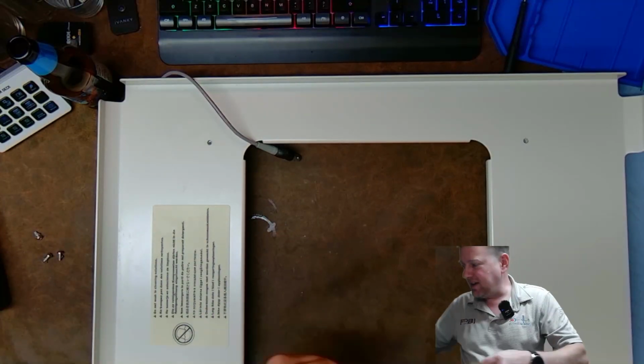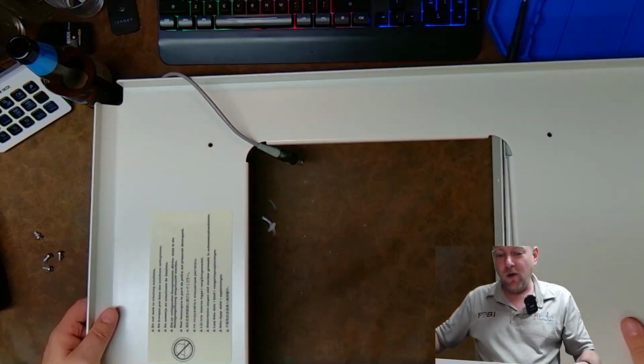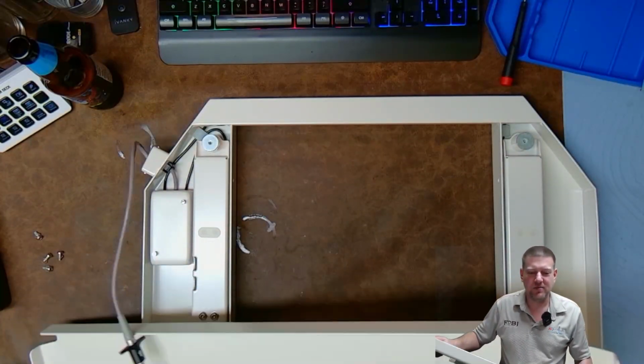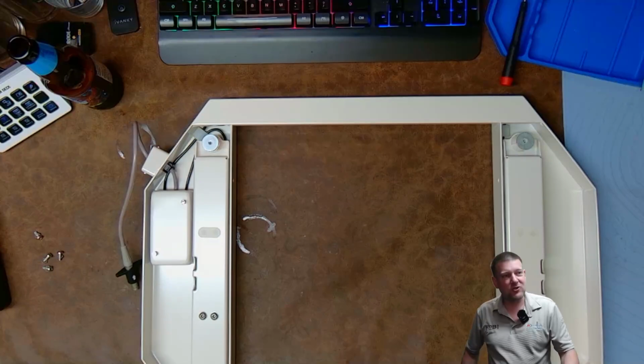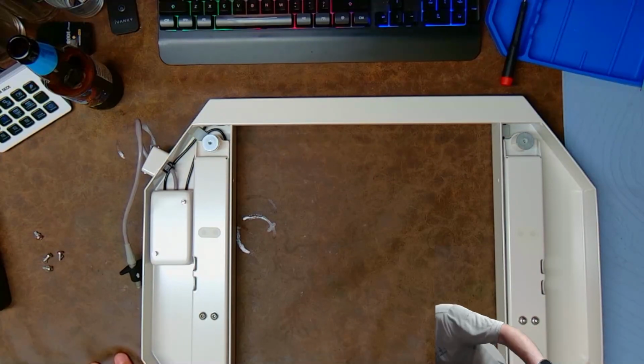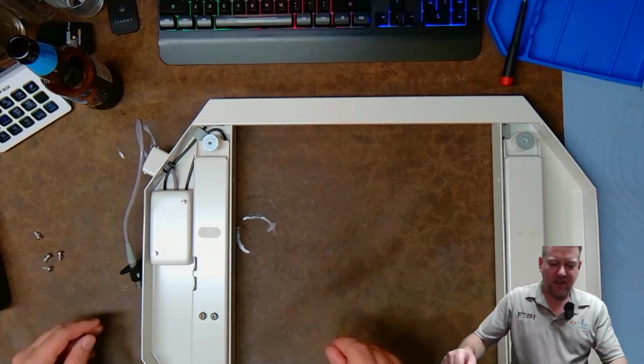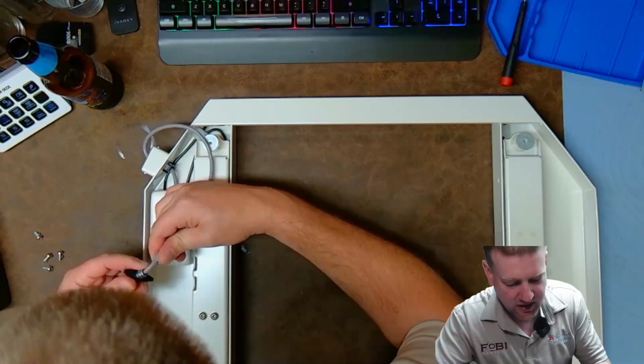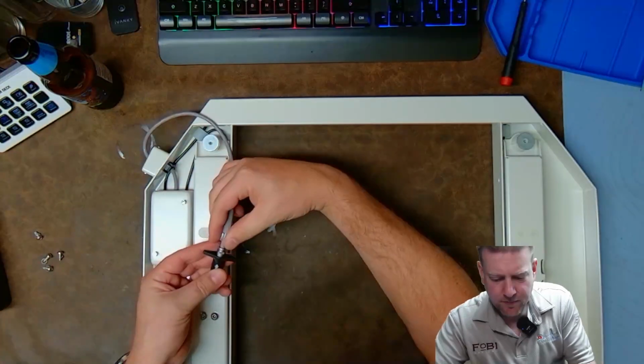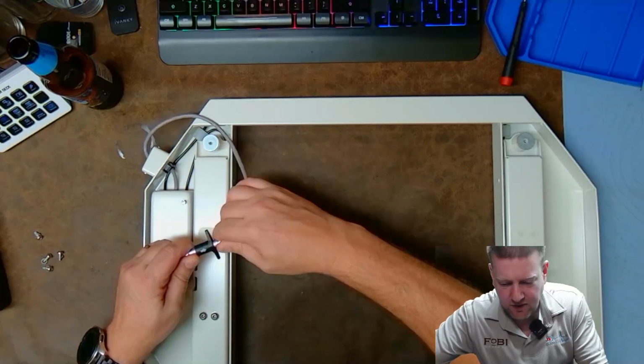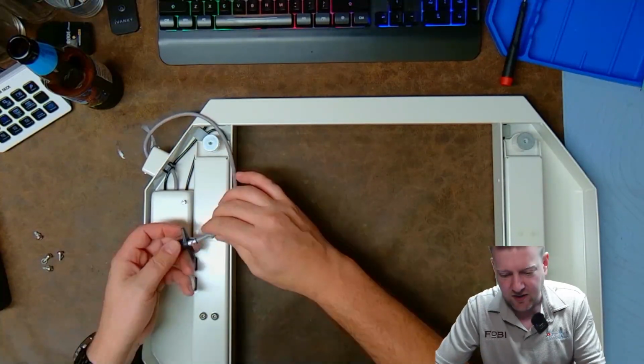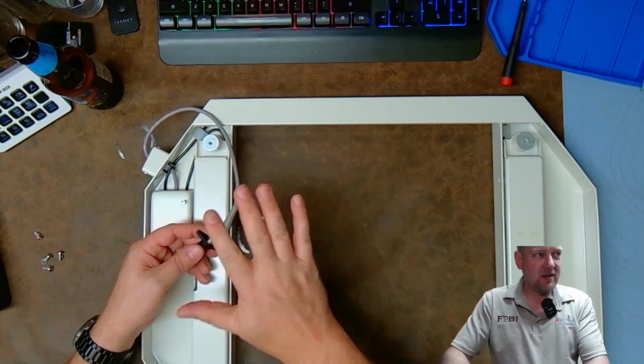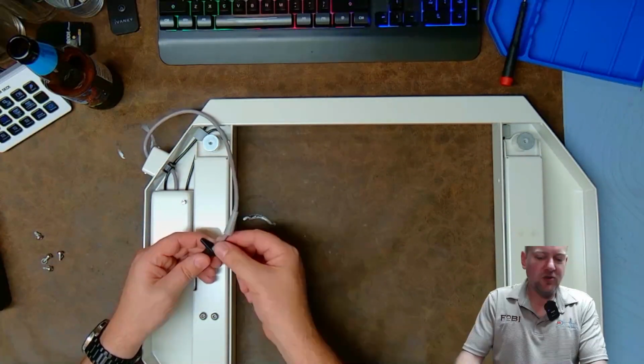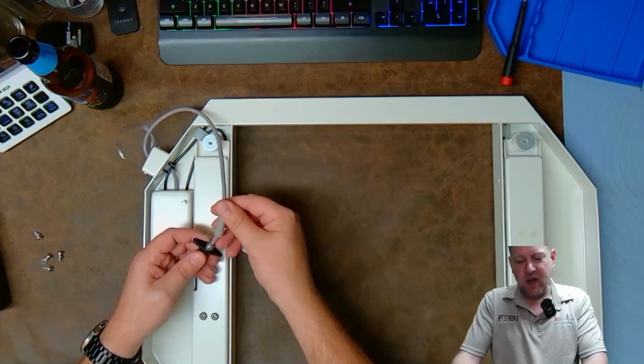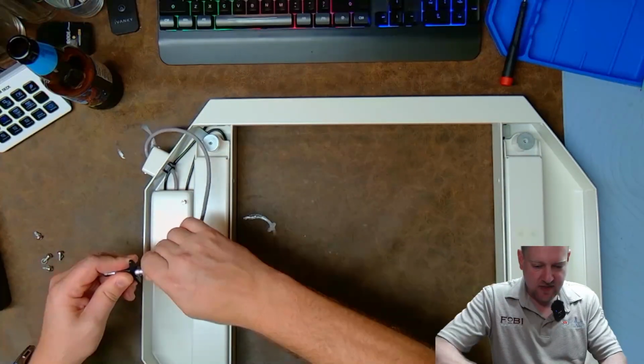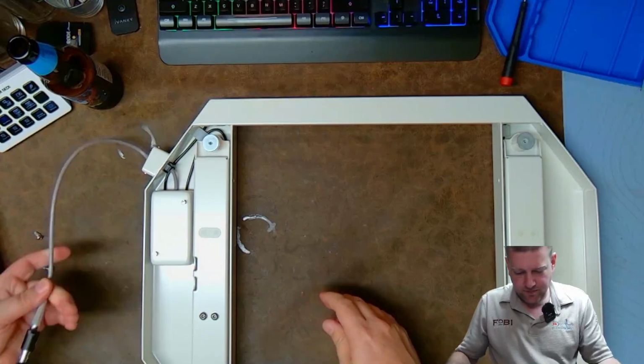Many of these devices that I have checked all over the place, many different hospitals, they are just straight up not calibrated. They're way off. Why are they so far off? Are Biomeds not calibrating these on their own? So I'm checking right here because sometimes these Lemo style round connectors, the rear end, not necessarily on the scales, but on other devices, this part here gets loose and then the cable will want to spin, so it breaks conductors. I don't think that that is the issue on this one.